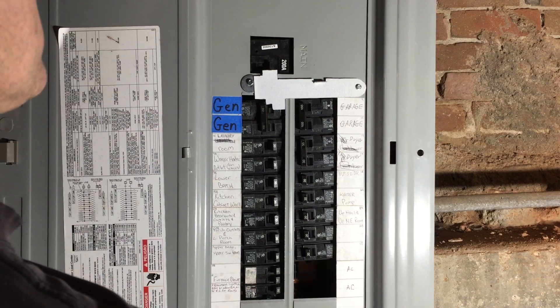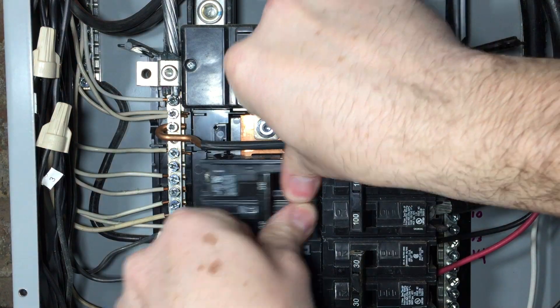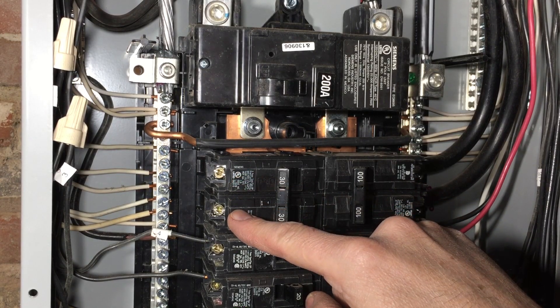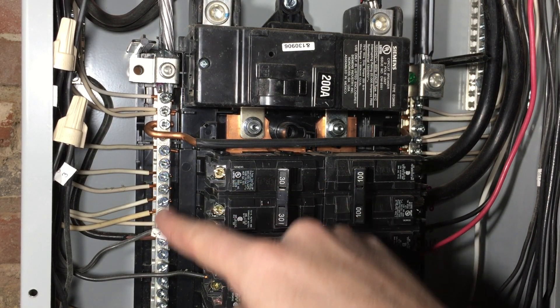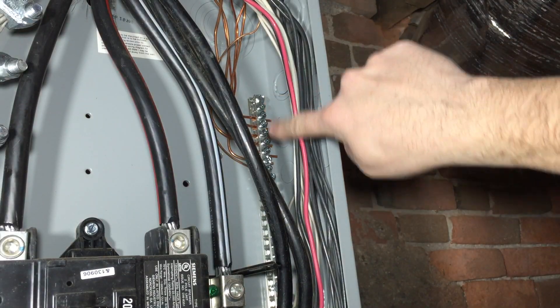To mount the circuit breaker, you take off the front of the electrical panel, put the breaker in at an angle like this, and push down. Your black and red wires go here. Your white wire goes on the neutral bar with the other white wires, and your ground wire goes up on the ground bar.